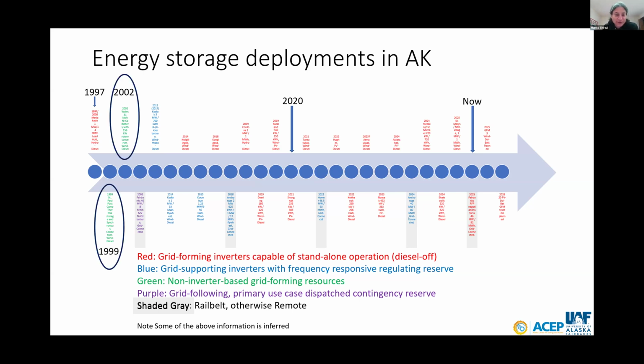And the next two are interesting, shown in green. These were non-inverter based grid forming resources, but were still working towards the goal of reducing diesel fuel use in these diesel-based microgrids. The holy grail is diesel off, because when you leave a diesel on, you have to run it at a minimum load to prevent wet stacking and health problems with the engine. This means you're consuming quite a bit of fuel just to have this engine on as spinning reserve. So if you can have an asset that can provide that reserve without being so expensive at no load, you can gain a lot of fuel savings.